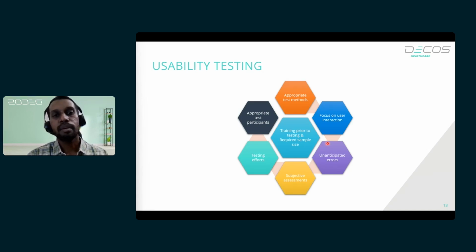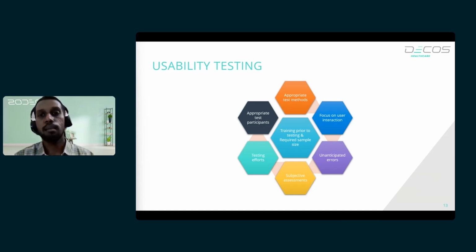And the next is training prior to testing. Say it is going to be a CT, an X-ray machine or an MR machine. It is going to be a very huge device involving a very large amount of cost, and the person who goes through this device is also going to get exposed to a certain amount of radiation, right? If a person who doesn't have any prerequisite knowledge is exposed to this device working, and instead of giving 0.5 radiation, I give 1, the impact of radiation can have a severe impact on the end user. So training prior to using the device is very critical, so that the person will have some prerequisite knowledge on how the device is working, and that can enable him to perform the intended actions correctly.